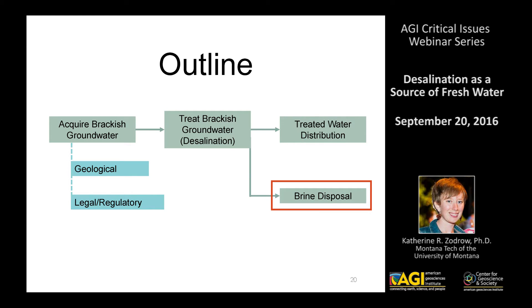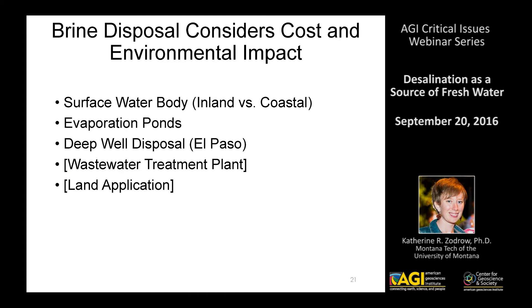After we desalinate our water and distribute it, we have to figure out what to do with the brine. The brine disposal methods seen in Texas — as reported in the Texas desalination plant database — include surface water body disposal (inland, this can be an issue; coastal, less so, but mixing is required), evaporation ponds (Texas has a lot of land, it's hot, and we have a lot of sun, so evaporation ponds work quite well), and deep well disposal — the Kay Bailey Hutchison plant in El Paso disposes of brine through deep wells. There's also some disposal to wastewater treatment plants, and some land application.